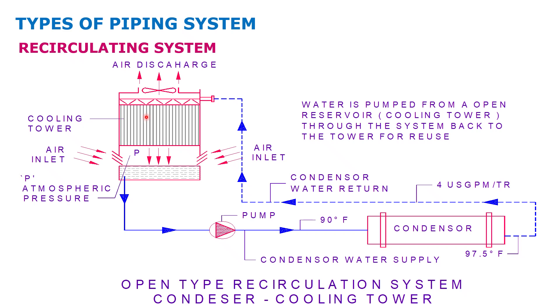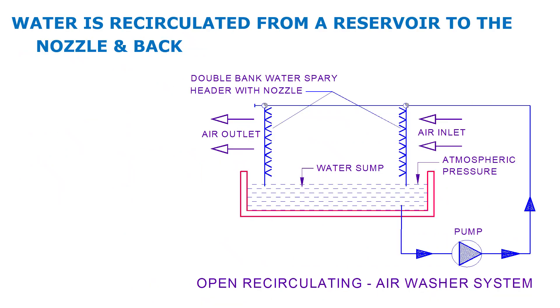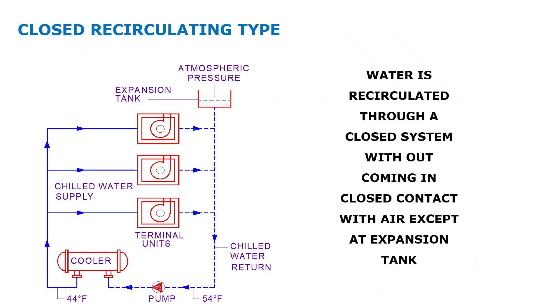The recirculating system uses a cooling tower, where water goes from the cooling tower to the condenser, rejects heat with the help of a fan, and is recirculated. Water quality plays a very important role in deciding how many times water is circulated. For air washers, water is collected, pumped over an evaporative or cell-deck pad, and with the help of a fan the air temperature is reduced before being delivered to the application area. This is again an open loop system.